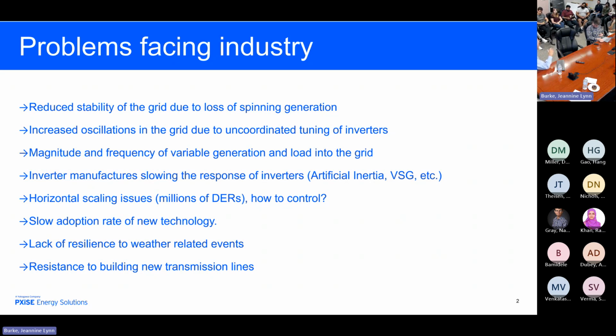You may or may not be aware that most commercial inverters today only speak Modbus protocol. Modbus protocol really has no limits on the speed, but in fact, because of limitations in the network communications, the fact that there has to be an acknowledgement come back from every command slows it down. So the best we can do today is 5 hertz control. Our position is we need 60 hertz control at the inverter level. So I tell it to go to 10, I want it to get there in 16 milliseconds. That's not happening today.